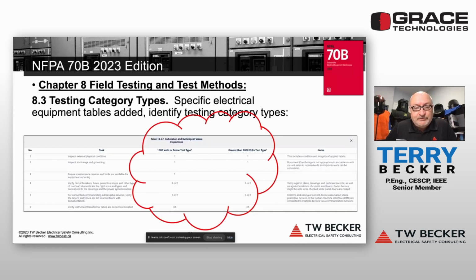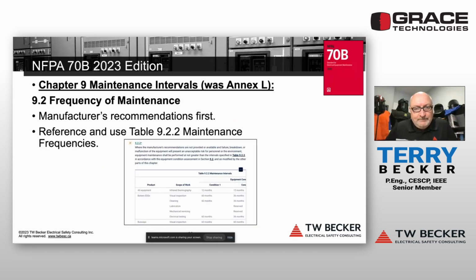There's the example table - this one's for substation and switchgear visual inspections. You can see the task, and it shows the different testing category types recommended, in this case voltage dependent. In chapter 9, the maintenance intervals were moved from Annex L.